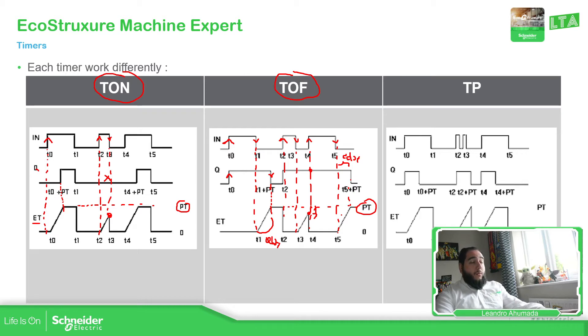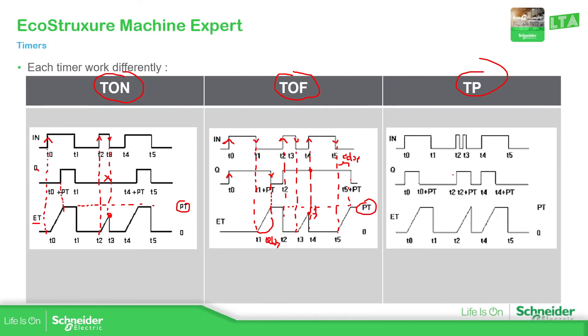The third timer is the T_P — timer pulse. When you activate the input, the output will be automatically on, but it will stay on only for the duration configured in the preset PT — just one time. It doesn't matter if you trigger the input too many times; it will execute the output only just one time.